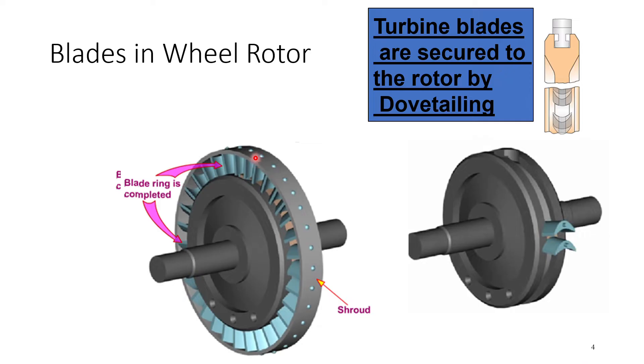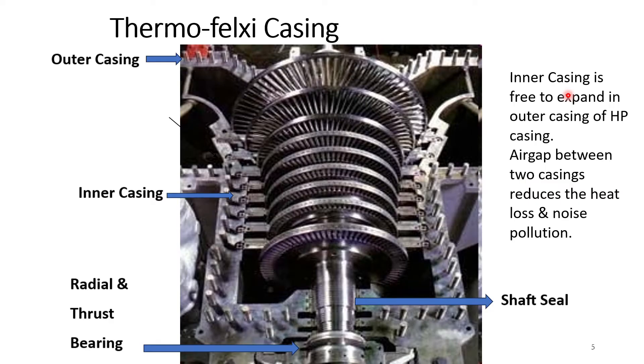The rotor is made of a number of wheels connected on a shaft. On the shaft there is a circular wheel called a hub. On the hub, each blade is inserted one by one and then finally it is sealed. The blades are interconnected with a shroud to give stiffness. The blades are secured to the rotor by a procedure called dovetailing, which is shown on the extreme top right hand side.